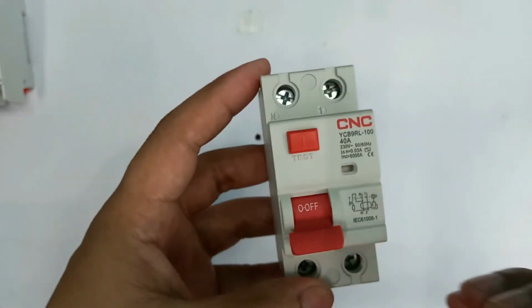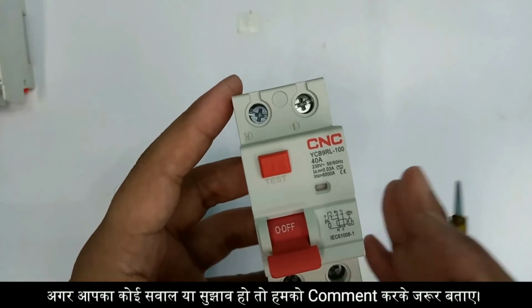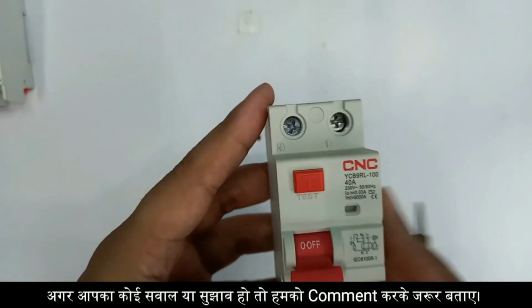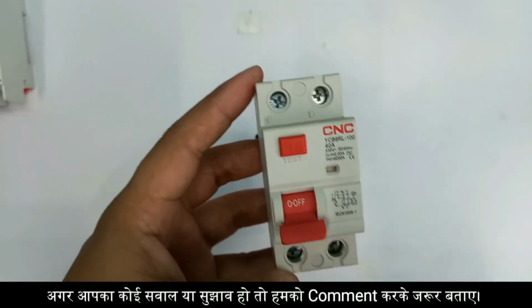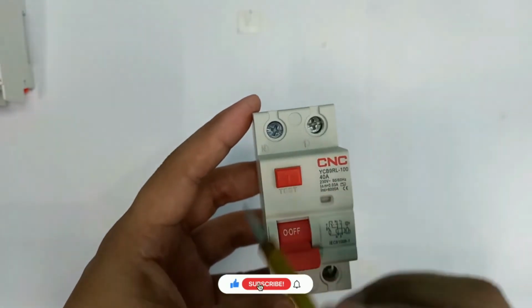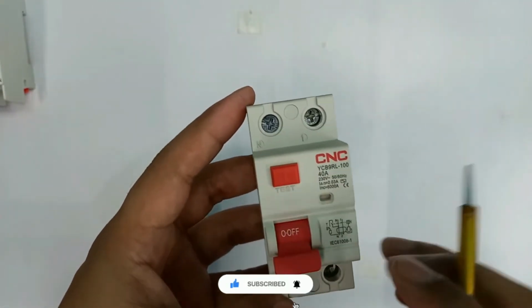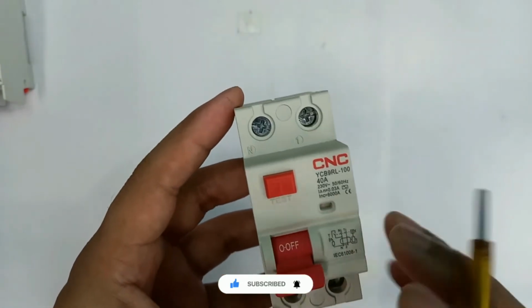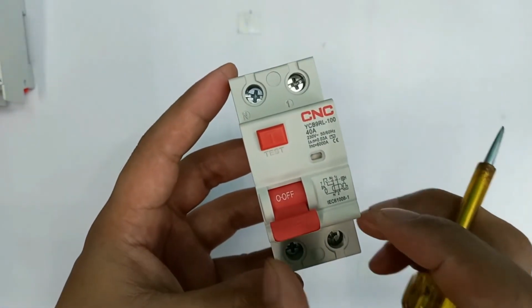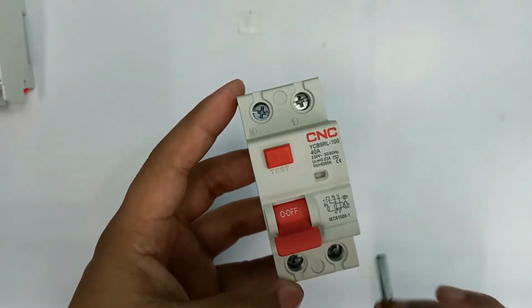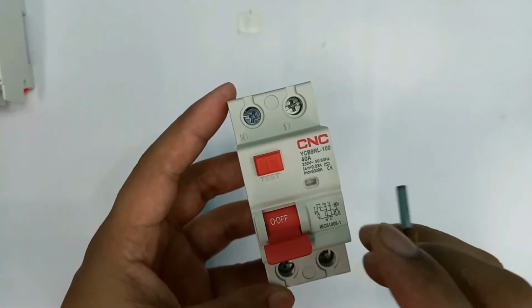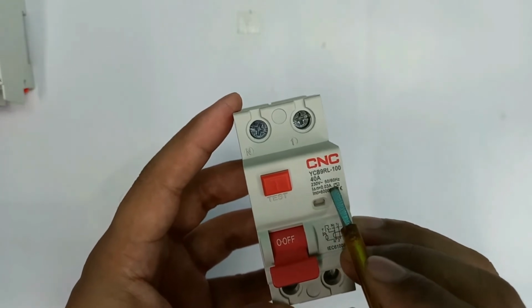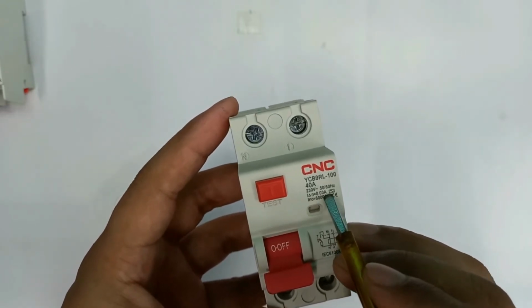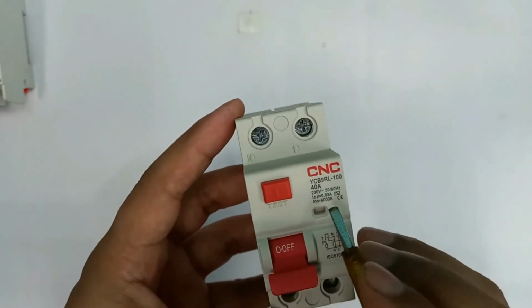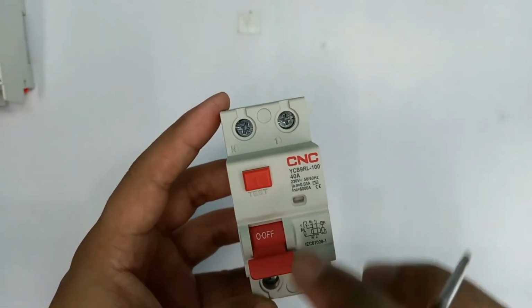Now in the last, if you will see here, that is the minimum leakage current. We have already discussed what minimum leakage current is and what its significance is. So simply, suppose if 6 ampere you are giving at the one side, at the neutral side also 6 ampere should go. If 6 ampere is coming, 6 ampere should go. If it does not happen, then it will be an unbalanced load, right? So in that case, what will happen? Simply your protective device will trip out, and the minimum current should be 30 milliampere.